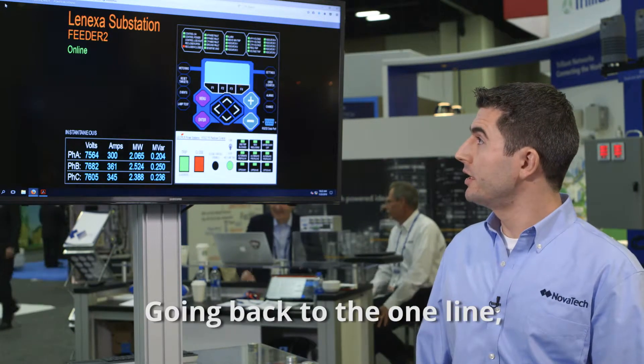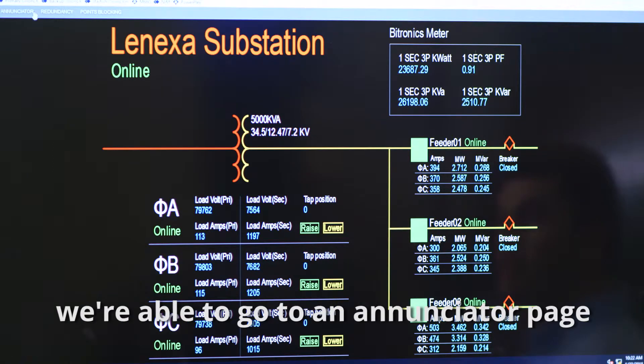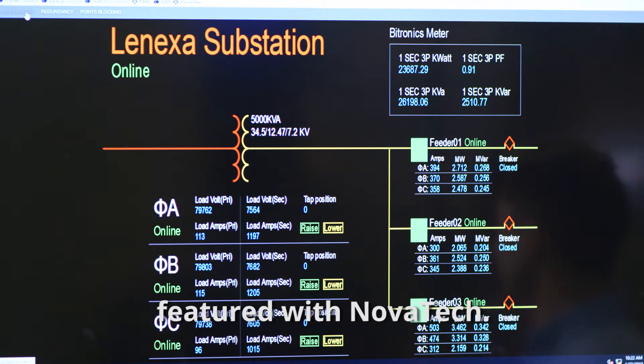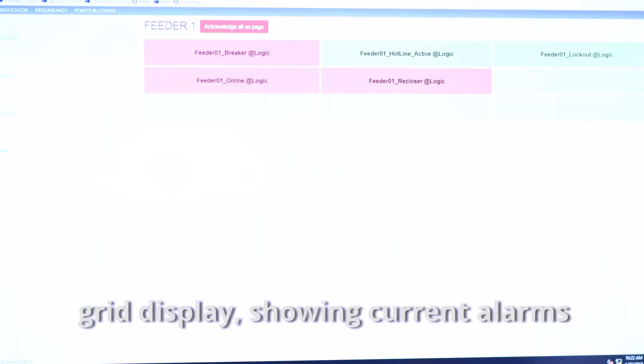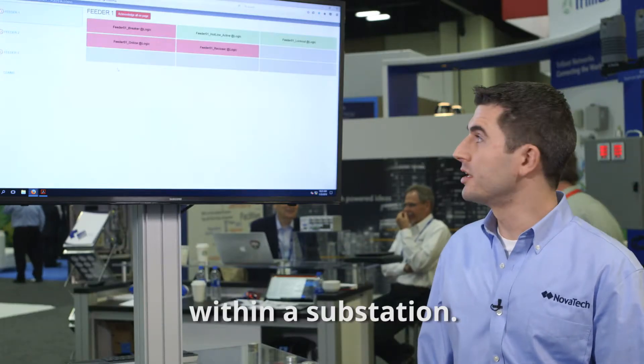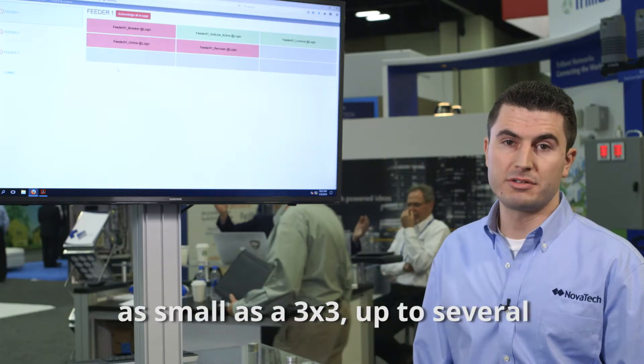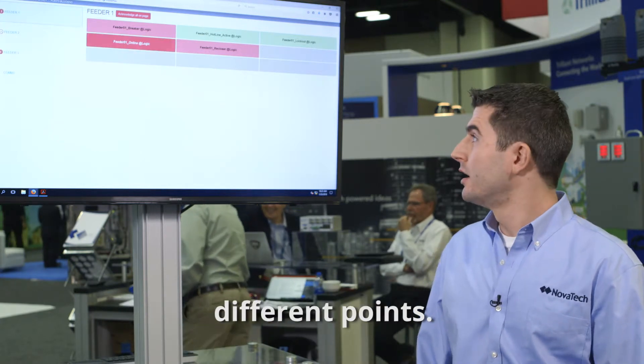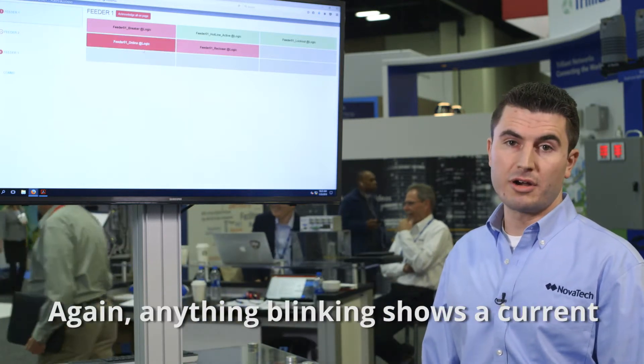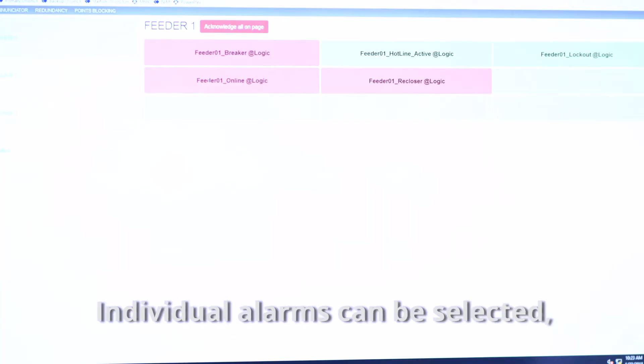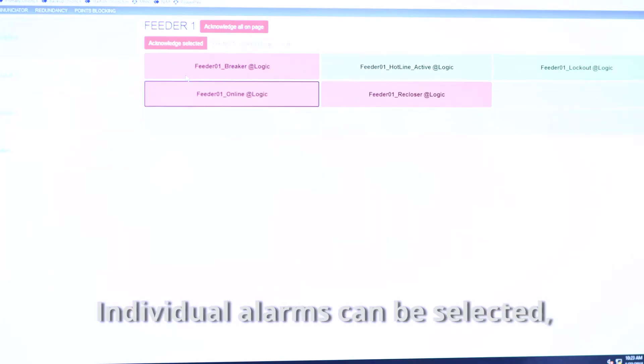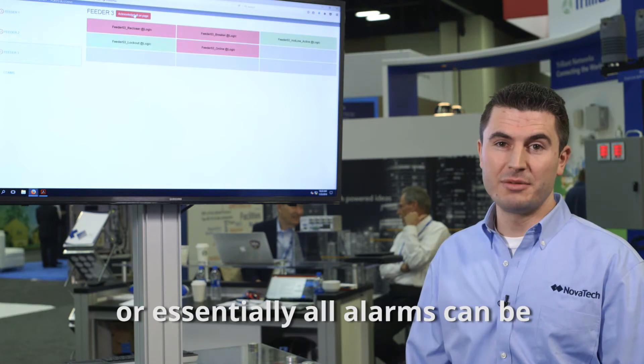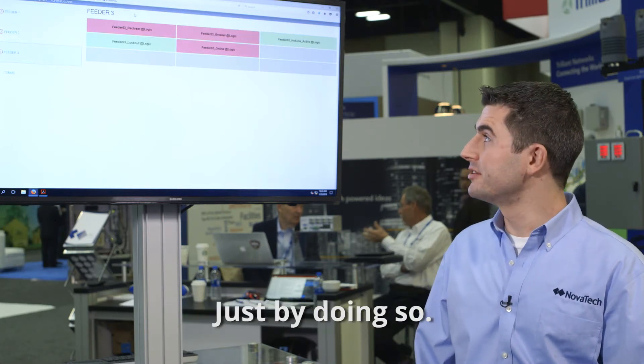Going back to the one line, we're able to go to an annunciator page featured with NovaTech. This is an easily configured grid display showing current alarms within a substation. It can be a grid pattern ranging from as small as three by three up to several different points. Anything blinking shows a current unacknowledged alarm. Individual alarms can be selected and acknowledged, or all alarms can be acknowledged at once.